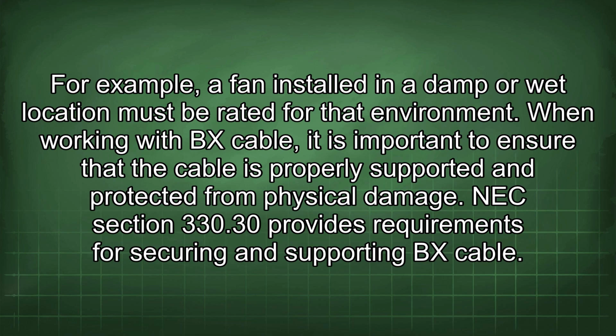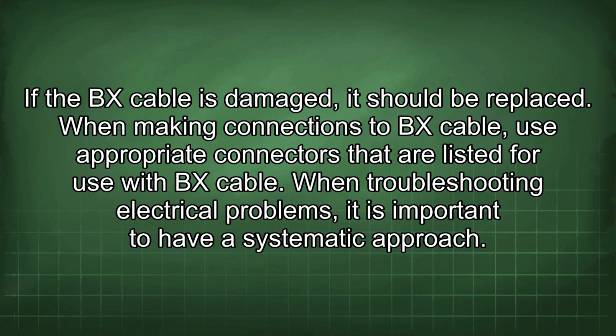When working with BX cable, it is important to ensure that the cable is properly supported and protected from physical damage. NEC Section 330.30 provides requirements for securing and supporting BX cable. If the BX cable is damaged, it should be replaced. When making connections to BX cable, use appropriate connectors that are listed for use with BX cable.